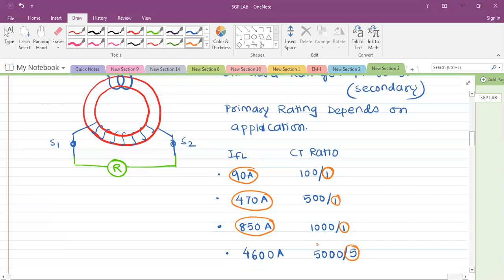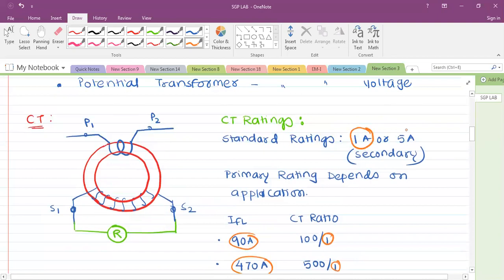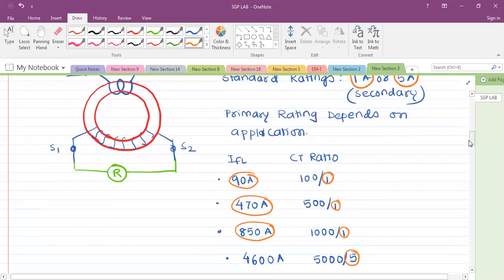We'll discuss later why you should select 1 ampere or 5 ampere. So understand that the secondary rating can be either 1 ampere or 5 ampere, but the primary rating you may find in a range - 100 bar 1, 200 bar 1, 300 bar 1, 400, 500 bar 1, and so on. The primary rating is decided based on the application where you want to connect the CT.